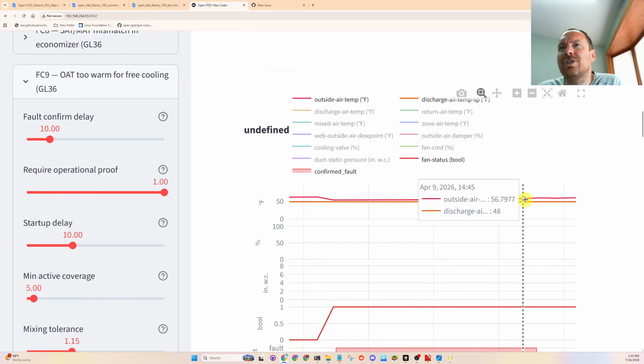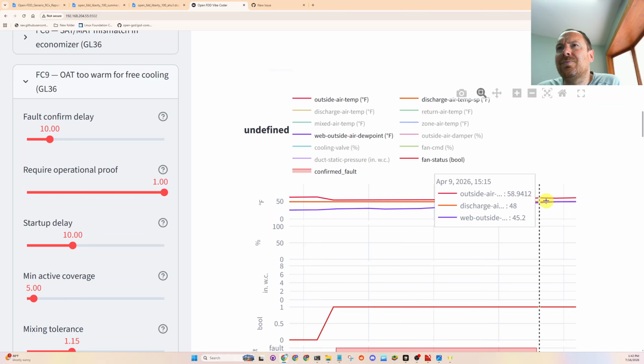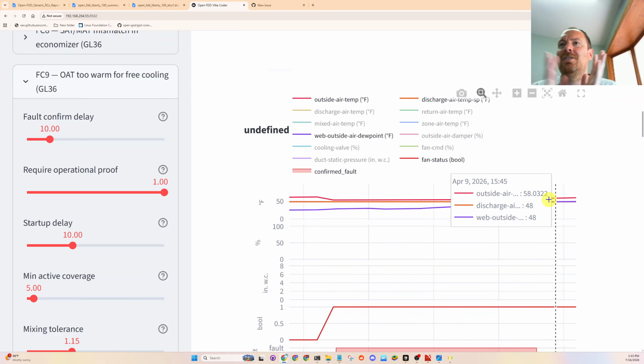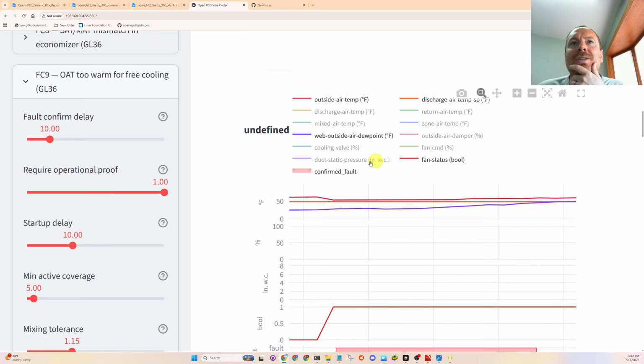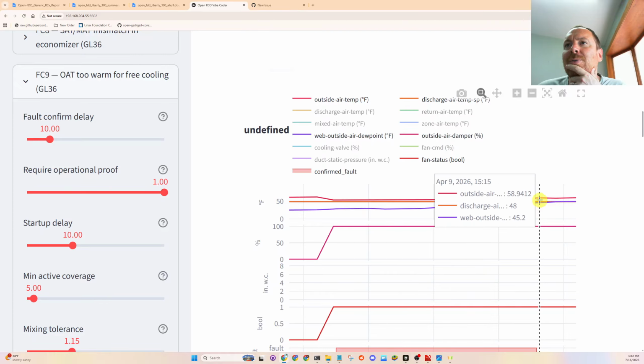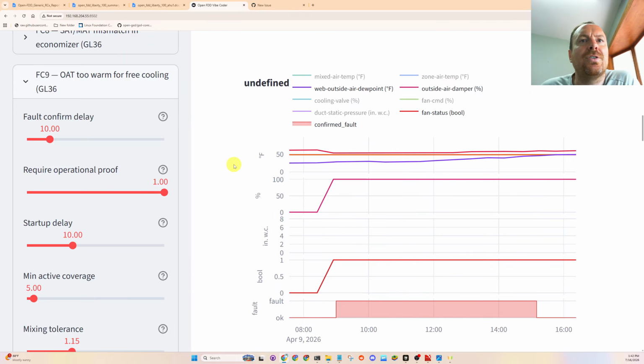So right here, the outside air temperature is 58 degrees and the discharge air set point is 48, but let's look at dew point. Yeah, you're well within. So the air handling unit is in 100% outside air mode, and I'm going to ignore this. This is doing exactly what it's supposed to be doing. The really odd thing is that the discharge air temp set point is so low. Like we talked about, there are other unknown mechanical problems in the building that we just don't know why they need to have such a low set point.